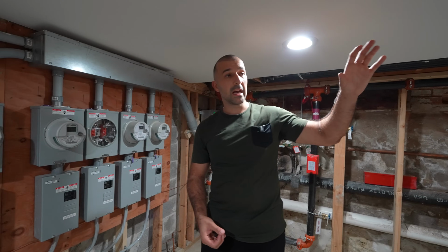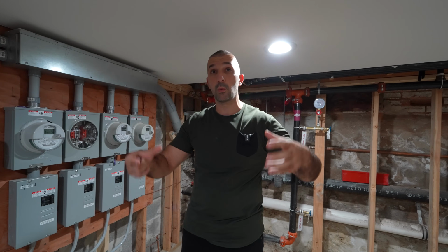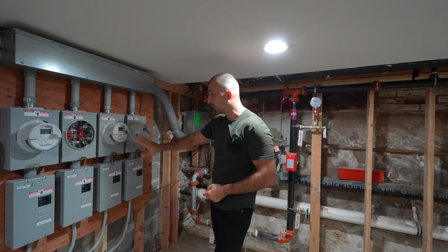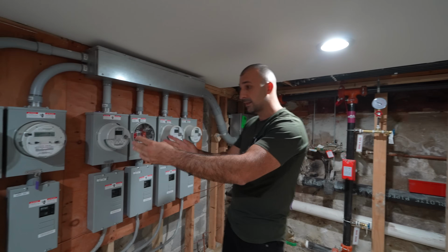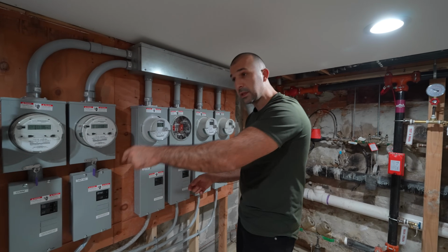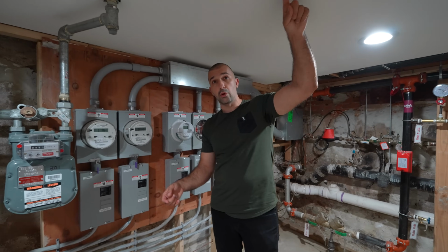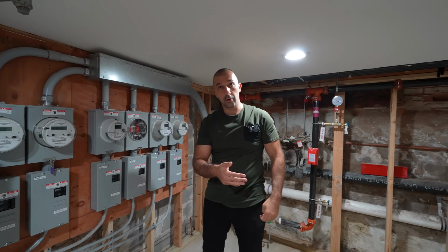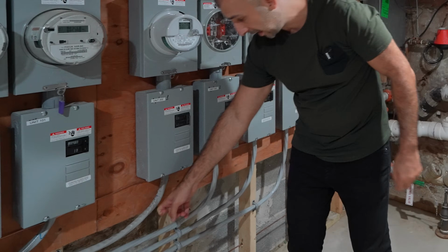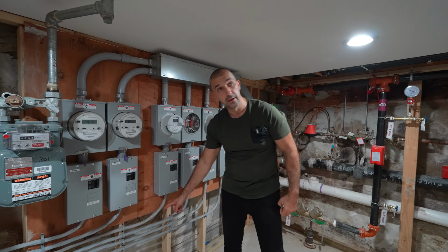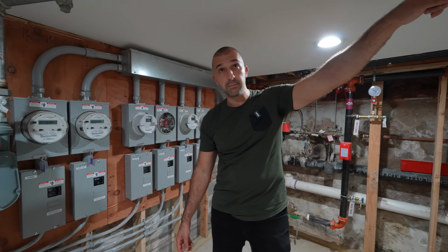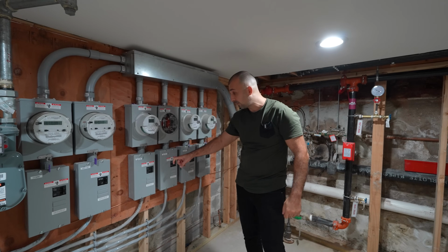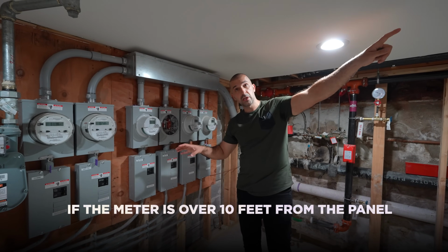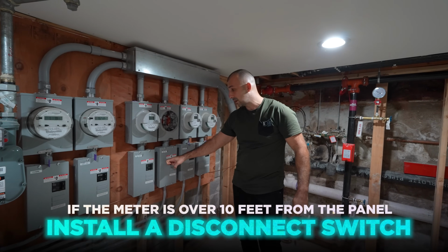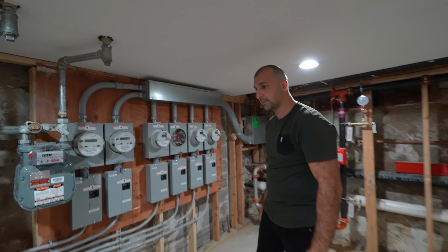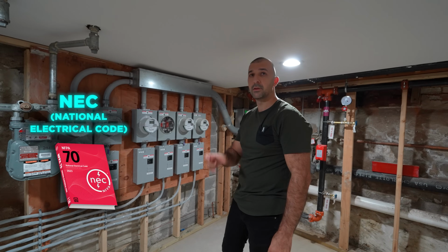This is how people do it, the old way, the wrong way, the cheap way. From this meter, people would put electrical boxes with all the breakers and little wires that go up to the upstairs, third floor, second floor. That's too long of a run. Instead of running that, I'm running a thick cable, which is 100 amps, all the way to the unit. Because there's a distance of more than 10 feet from the meter to the electrical panel, you gotta put a disconnect switch. That's electrical law, there's people that write the NEC, they write the rules and regulations.